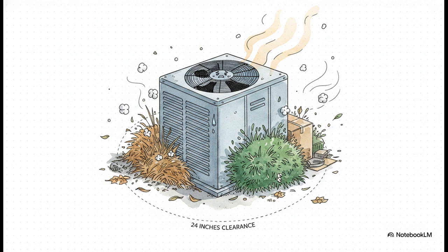Out in Kyle, things like grass clippings, leaves, and those fluffy cottonwood seeds accumulate super fast. If you let shrubs or yard storage encroach on that 2-foot barrier, you are literally suffocating the unit. Your condenser's entire job is to dump heat outside, and if you restrict its airflow, it works harder, spikes your energy bills, and causes the compressor to fail way before it should.